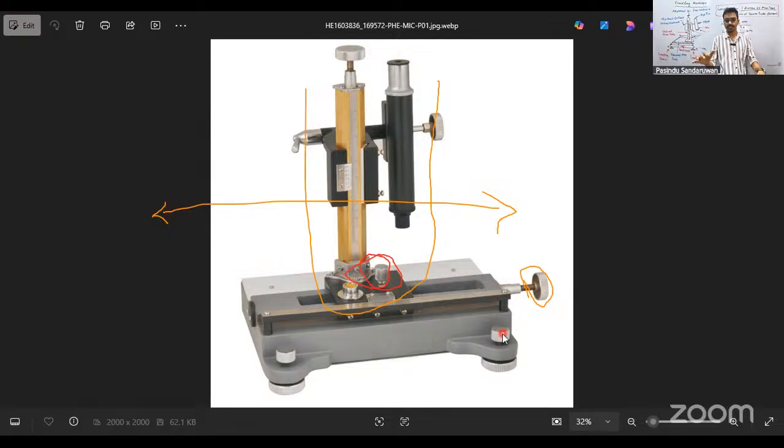The purpose is to level the instrument, right? And the leveling spirit level cannot be seen in this diagram. That is behind this setup, because that is a front elevation. In different instruments, that will be in different places. What I have drawn is an instrument with the spirit level in front of the instrument. In some instruments, that is behind the instrument.